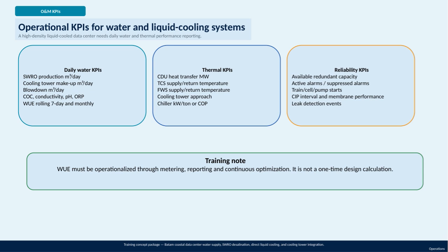On the thermal side, we focus on heat transfer performance at the cooling distribution unit in megawatts, supply and return temperatures at various points, such as a thermal control system and freshwater system, and the cooling tower approach temperature, which indicates how efficiently heat is being rejected to the atmosphere. Additionally, we evaluate chiller efficiency through kilowatts per ton of cooling or the coefficient of performance.